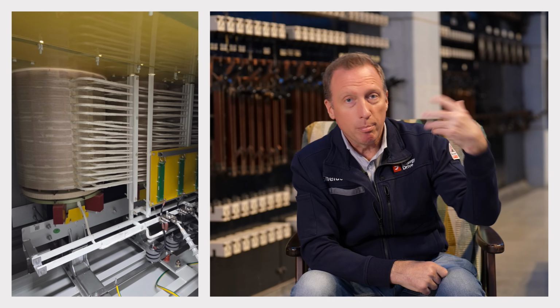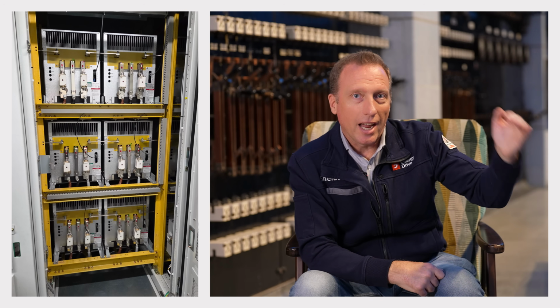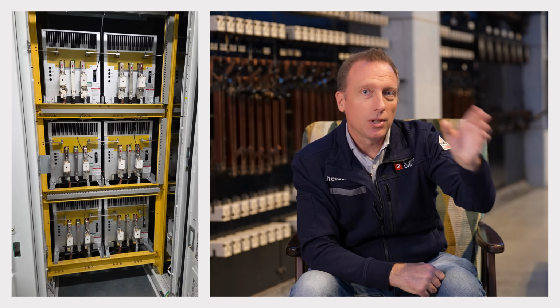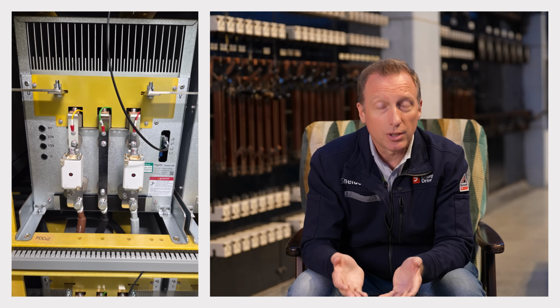And the VFD guys did this with a simple architecture. They solved a complex engineering challenge with architecture instead of complex electronics. So what did they do? They've got an input transformer, phase shifted and isolated secondaries. Those secondaries are each then connected to a power cell, a low voltage power cell, and those are connected in series. What does that mean? We're able to control the individual power cells, stack the voltages on top of each other, and instead of switching a large voltage, we can switch the voltage in smaller steps, which gives us that cleaner waveform. It's a beautiful sinusoidal wave, much kinder to electric motors.